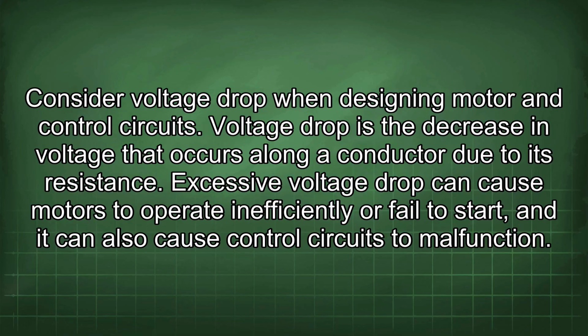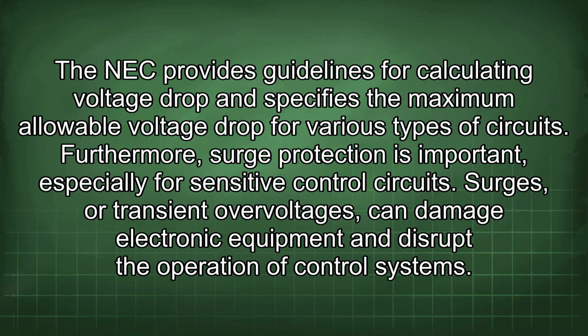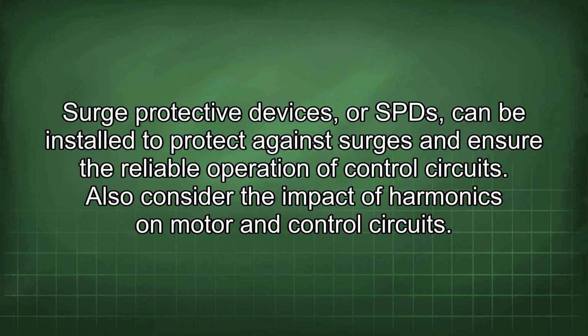Excessive voltage drop can cause motors to operate inefficiently or fail to start, and it can also cause control circuits to malfunction. The NEC provides guidelines for calculating voltage drop and specifies the maximum allowable voltage drop for various types of circuits. Furthermore, surge protection is important, especially for sensitive control circuits. Surges, or transient overvoltages, can damage electronic equipment and disrupt the operation of control systems. Surge protective devices, or SPDs, can be installed to protect against surges and ensure the reliable operation of control circuits.